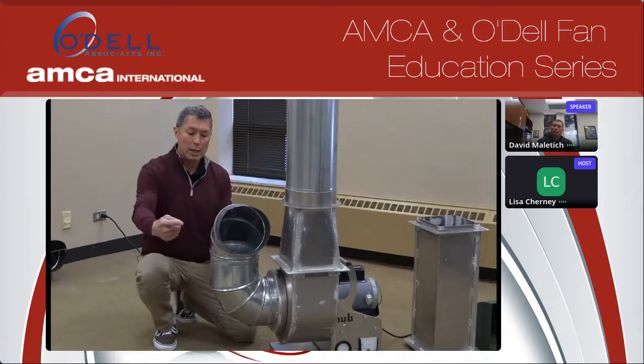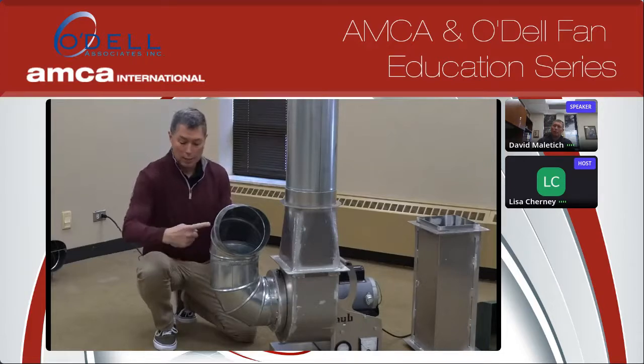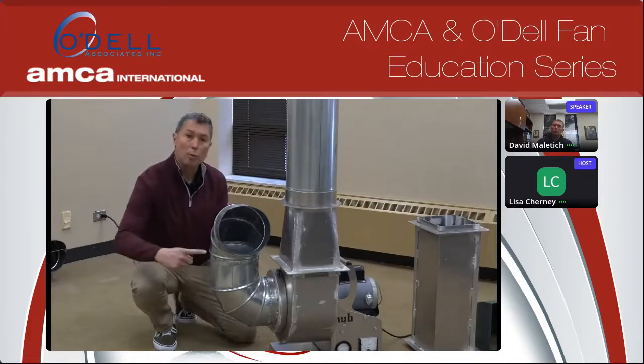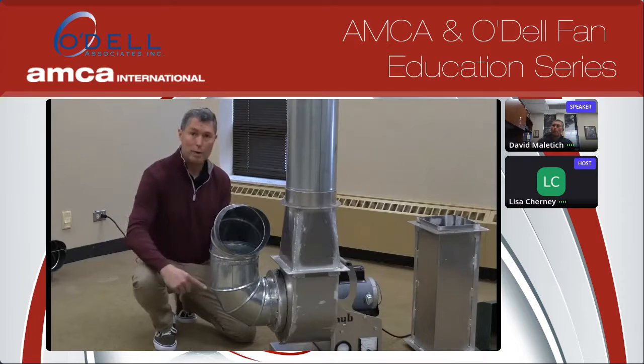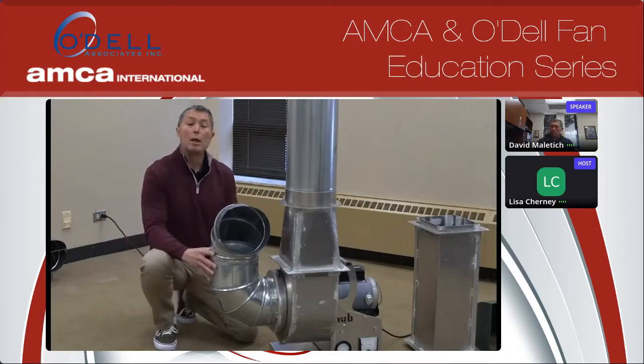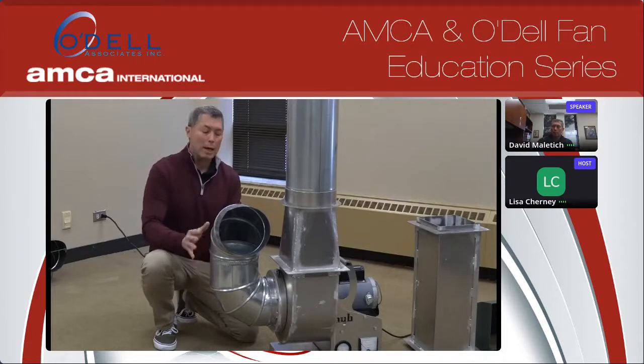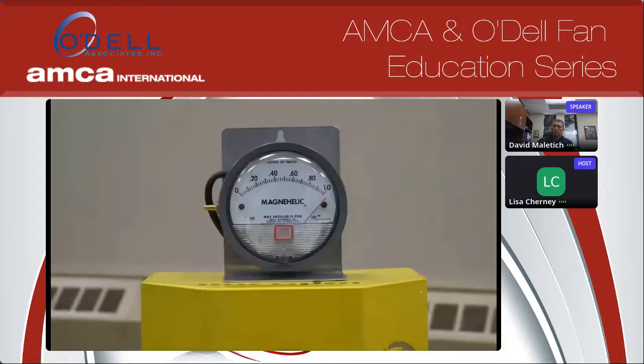Now in this case, air is coming in this direction. It wants to go into the corkscrew, so it's starting to pre-spin as it goes through the fan. Pre-spinning of the air means that the air is going in the same direction that the wheel is rotating, and the air cannot get moved as efficiently as it would be if it was coming in straight and laminar. And that results in a fan that's quieter, but also when you look at the Magnehelic gauge, you'll notice that the static pressure generated by the fan went down pretty significantly.